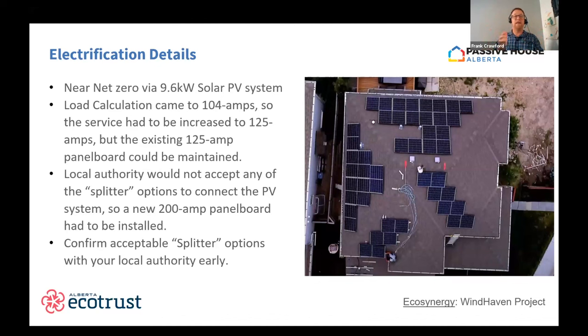But because of that, they did have to increase the electrical service from 100 to 125 amps. But that was the size of the panel before. Unfortunately, they were earlier on in the pilot program, so the splitter options to install that large solar PV system weren't acceptable to the local jurisdiction. So they actually had to pull out what otherwise could have been a useful 125 amp panel and put a 200 amp panel back in.